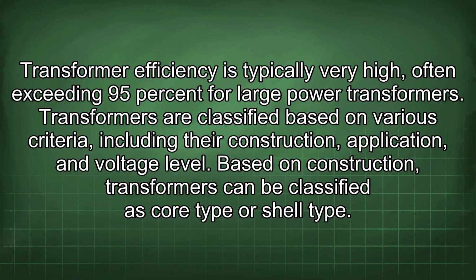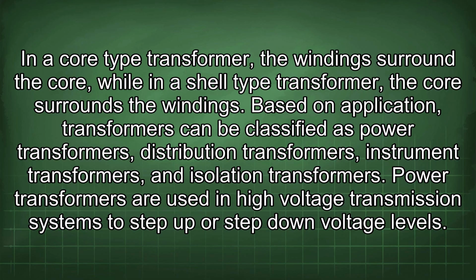Transformers are classified based on various criteria, including their construction, application, and voltage level. Based on construction, transformers can be classified as core type or shell type. In a core type transformer, the windings surround the core, while in a shell type transformer, the core surrounds the windings. Based on application, transformers can be classified as power transformers, distribution transformers, instrument transformers, and isolation transformers. Power transformers are used in high voltage transmission systems to step up or step down voltage levels.